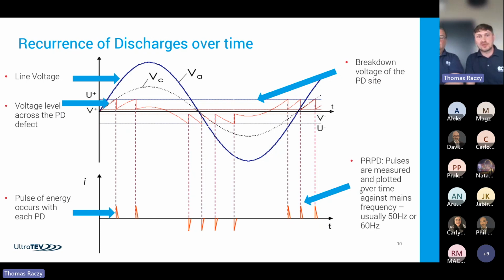Every time the voltage collapses across the gap, a PD is generated, a current pulse is generated as per the lower part of the screen. So you can appreciate that those occur typically on the rising positive edge of the power cycle and the rising negative edge of the power cycle. Therefore, for discharge from a source within an insulation or on the surface of the insulation, we will typically end up with two clusters of pulse distributions across the power cycle. So in the first quadrant of the sine wave and the third quadrant of the sine wave. And obviously all that will repeat every cycle.